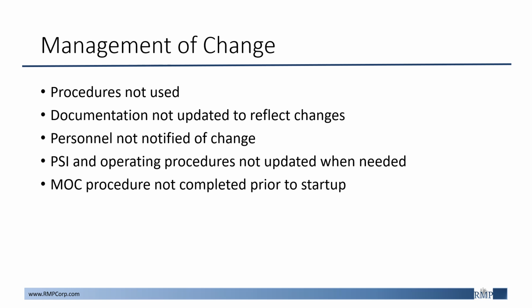So some tips to ensure your MOC procedures are meeting regulatory requirements would be to ensure that they consider the technical basis for proposed change, they look at the impact of change on safety and health, their operating procedures are identified and documented, the time period for changes in timeline are established, and finally, proper authorization is included via signing these documentation forms. You should have a member of personnel reviewing these management of change forms and ensuring that all aspects are looked at.